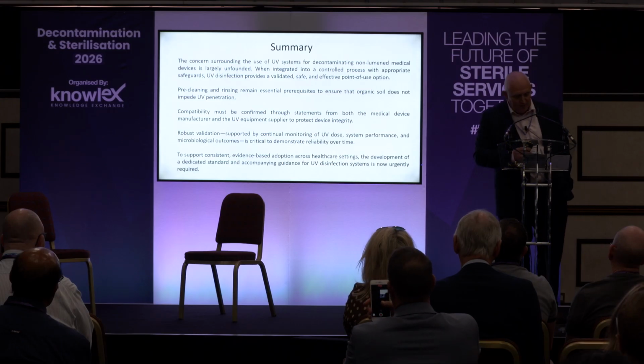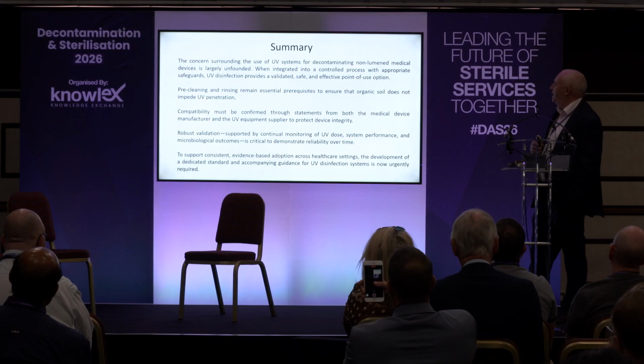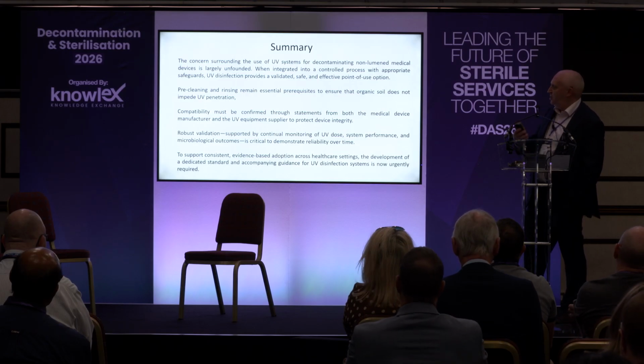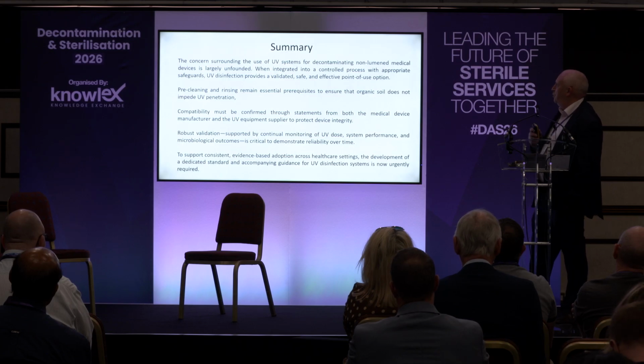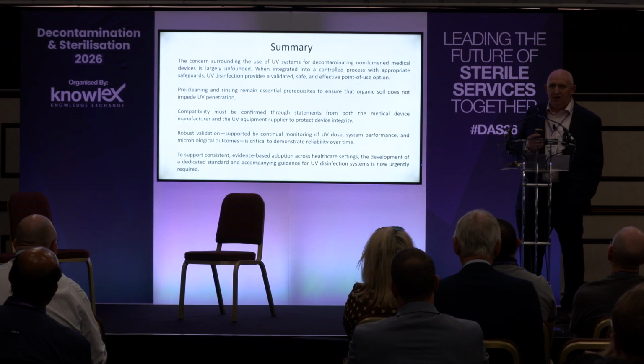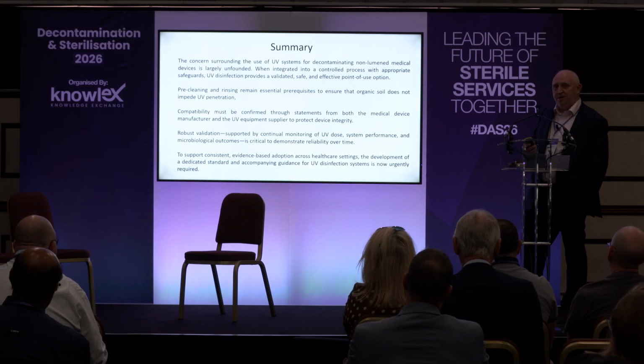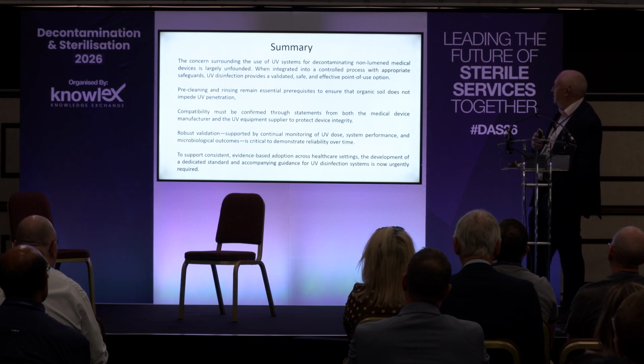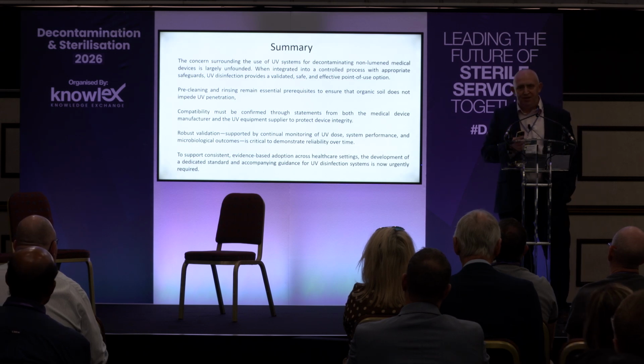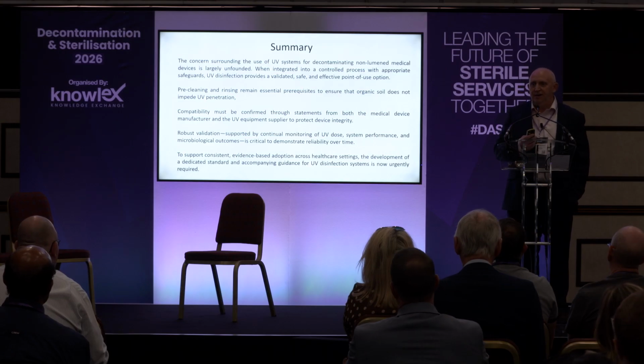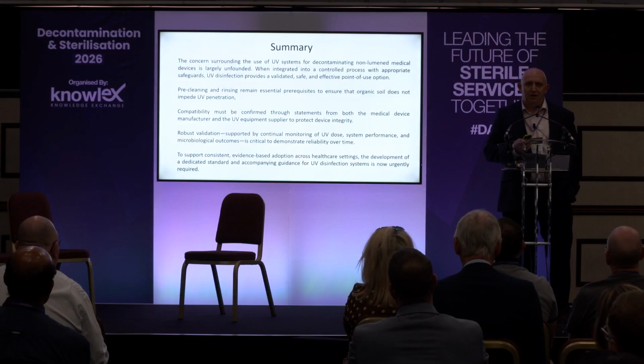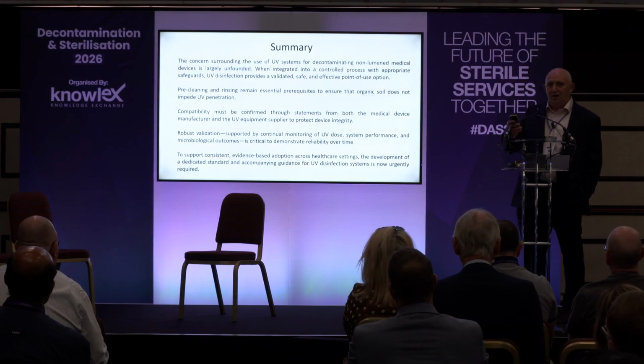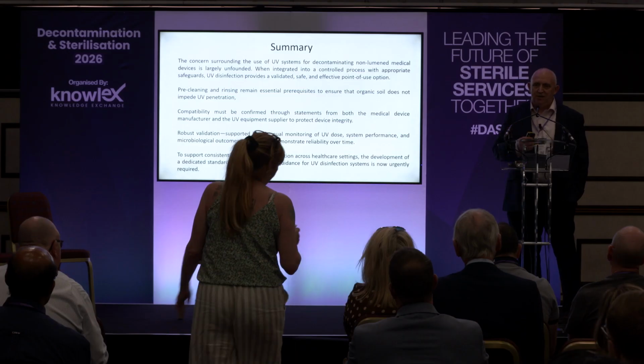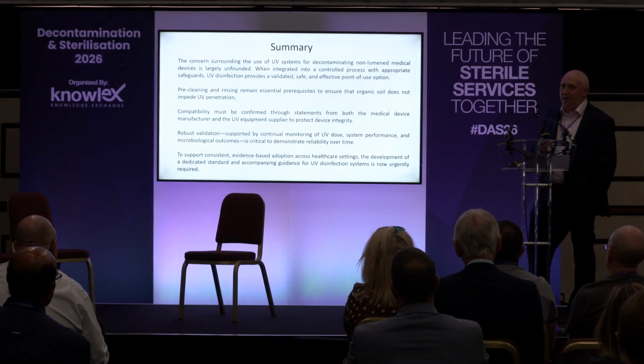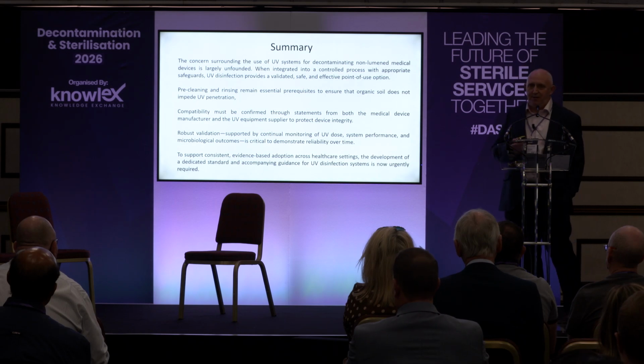So, to summarise, if we use these devices in the right context, UV of non-lumened medical devices can be achieved. Yeah? So concerns in some ways are unfounded, but we have got to make sure we take on the right context. Pre-cleaning and rinsing. Yeah, it's not just about putting some fairy liquid on it and just giving it an old wipe. We have to rinse the residues off there before it goes into the UV machine. That is where the compatibility issues and probe damage actually originates from, residues interacting with the UV. Compatibility must be confirmed, or at least indemnity agreements put in place.